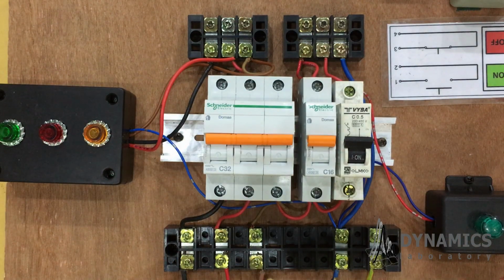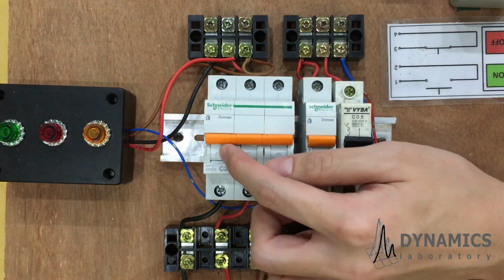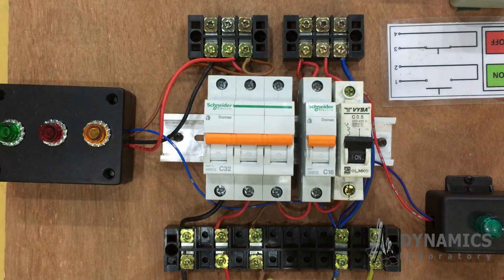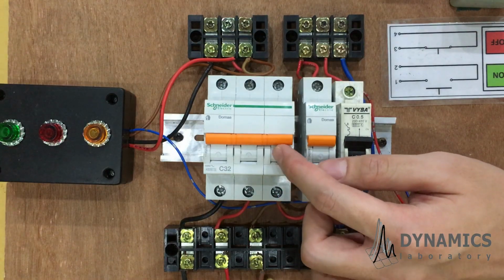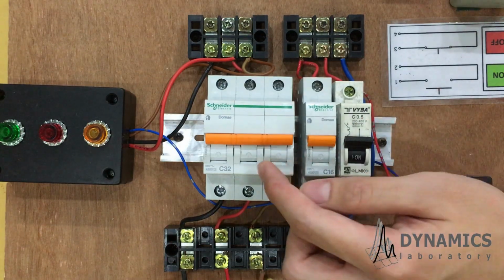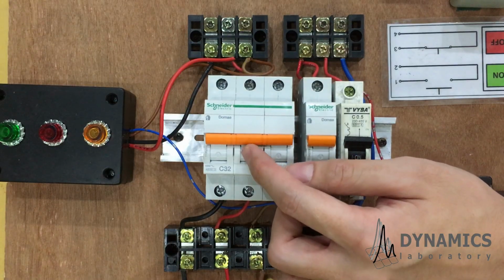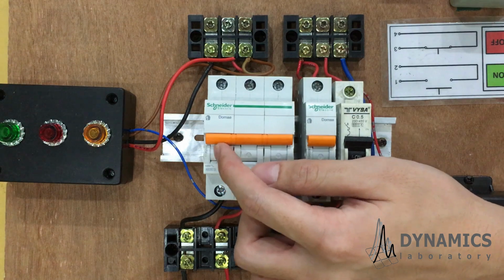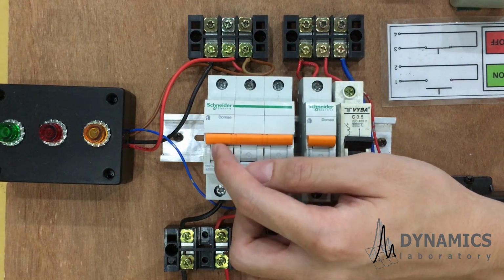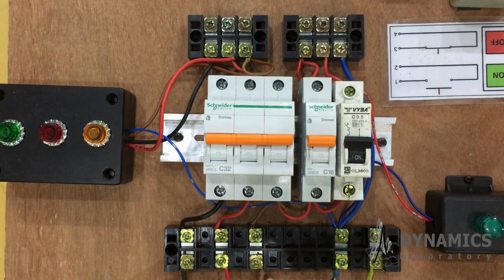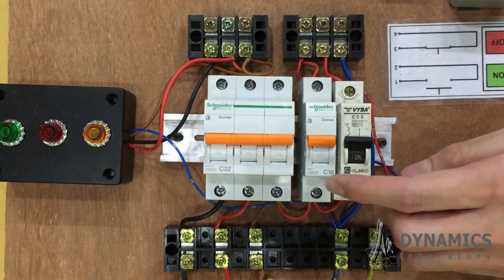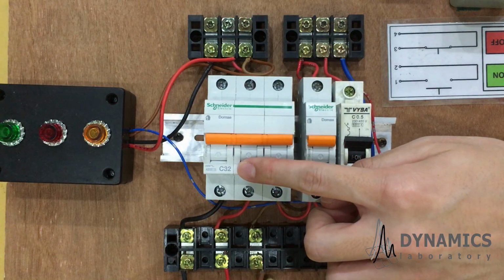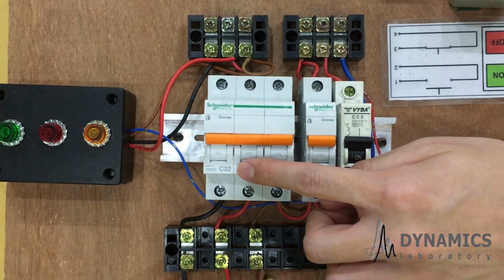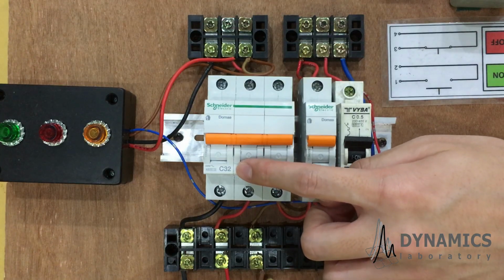This circuit breaker is called a three-phase circuit breaker, because each of these terminals will control one live terminal or one line. For example, this terminal is connected to R line. The middle terminal is connected to S line, and the last terminal is connected to T line or T terminal. The circuit breaker shows C32, which means the maximum current flow is 32 ampere.